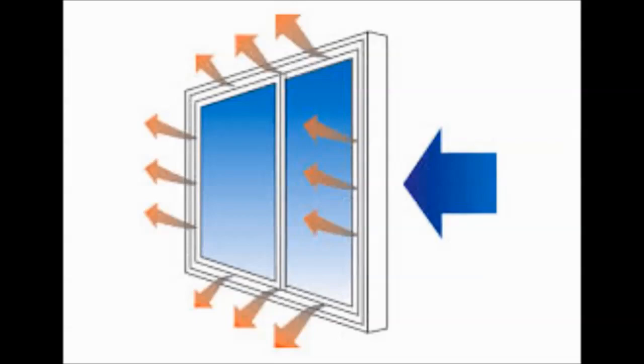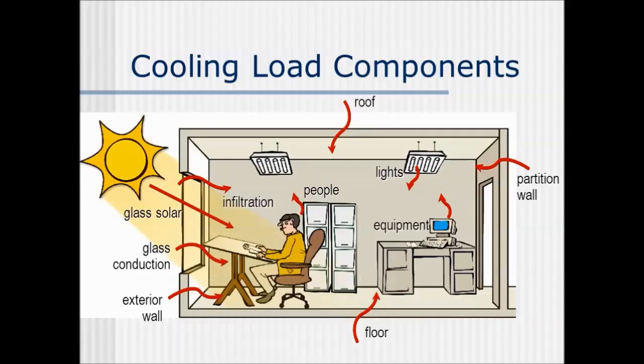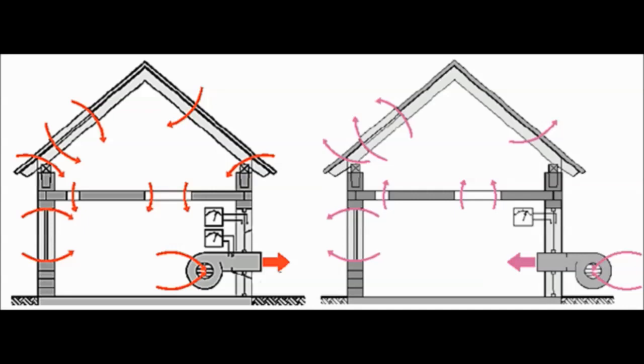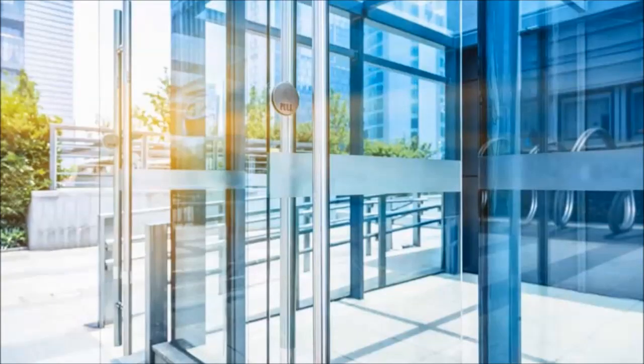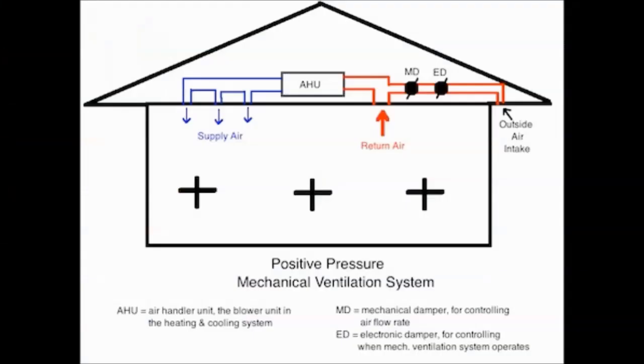Infiltration has a significant effect on the heating and cooling load of the building. Air movement through building openings and cracks is controlled by the pressure difference between inside and outside the building. Building's pressure at ground floor in cooling seasons is usually mechanically controlled by the HVAC system. The value of the pressure varies with an average of positive 10 pascals.